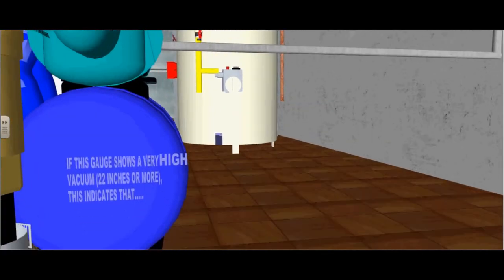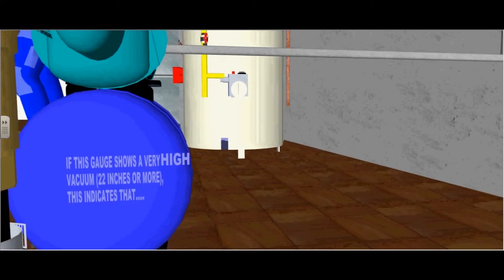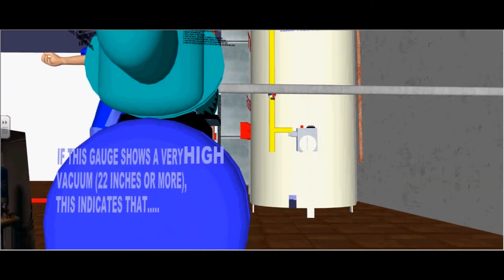If this gauge shows a very high vacuum of 22 inches or more, this will indicate that the end of the suction pipe is buried in mud, the foot valve is stuck closed, or the pump is not strong enough.